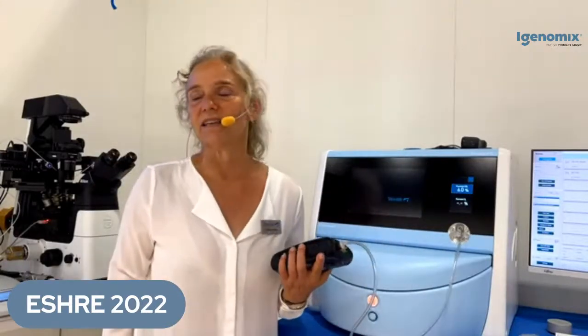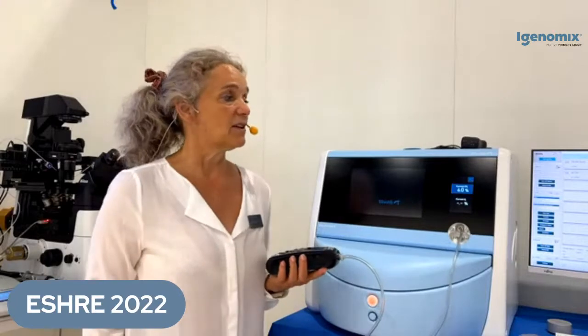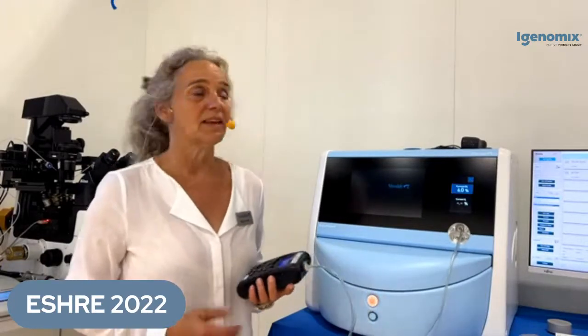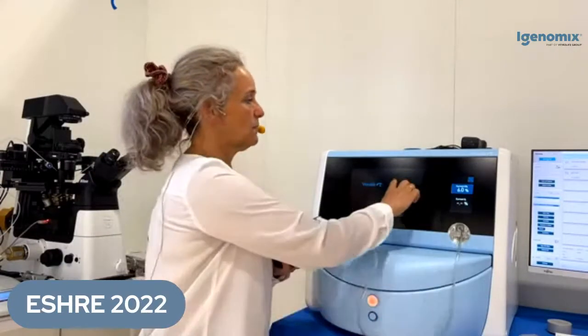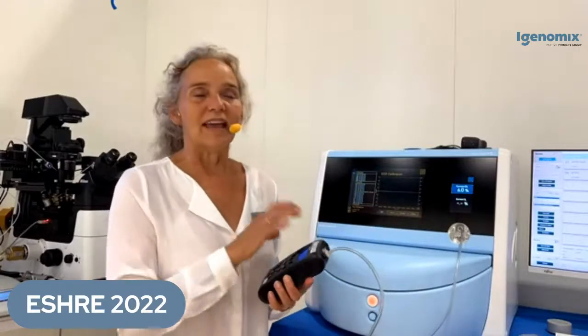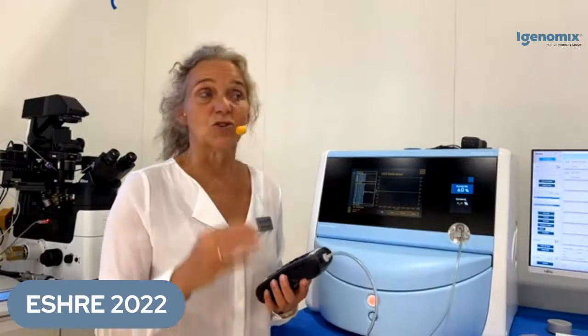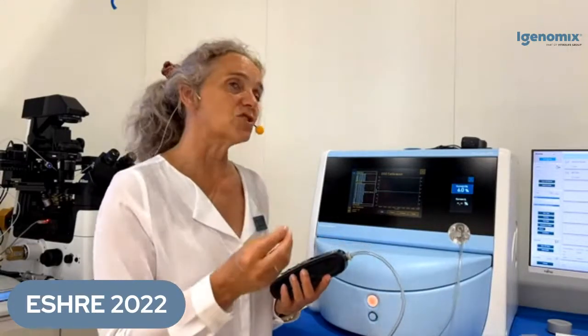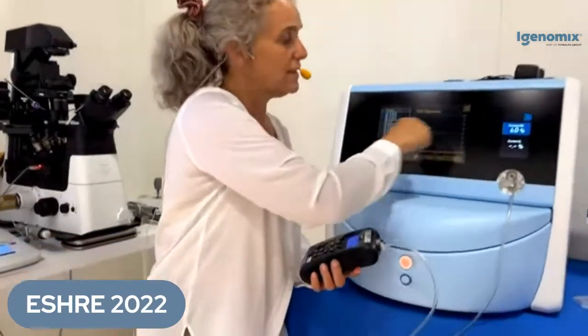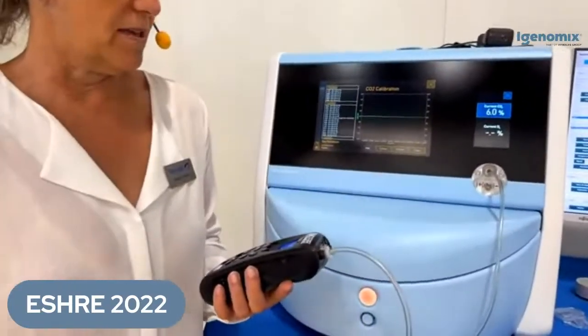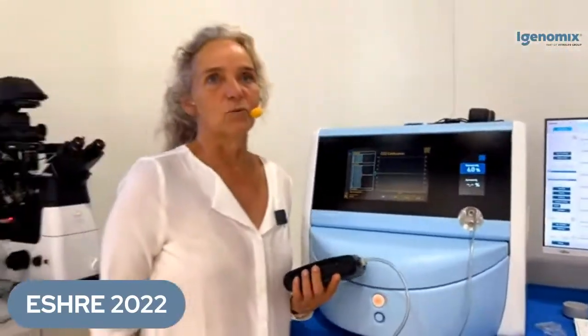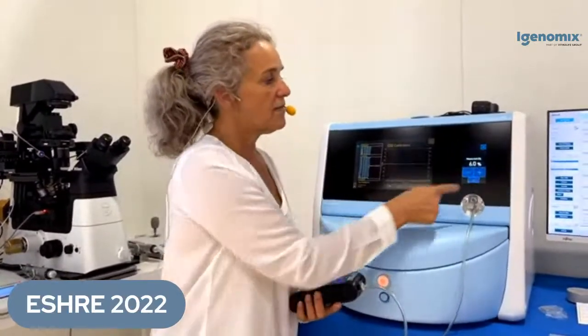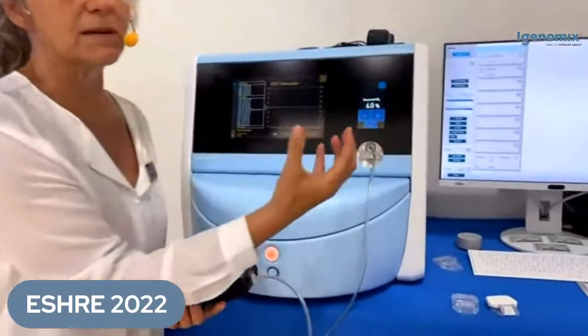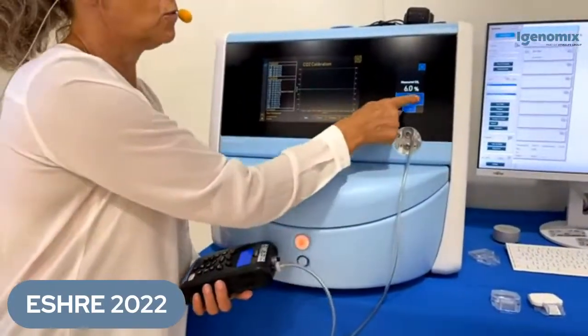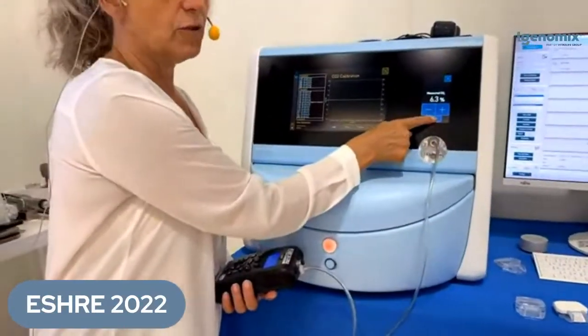So the set point here is 6.0%, according to the specification of the GTL media. And let's pretend that your analyzer shows 6.3%. So it means that we have to calibrate plus 0.3%. We can follow here the graph when it's stable. So it is actually quite stable now. But let's pretend that we should calibrate. Then you go into CO2, and then I will press 3 times on the plus, because each step reflects 0.1%. So 1, 2, 3, and then I confirm.